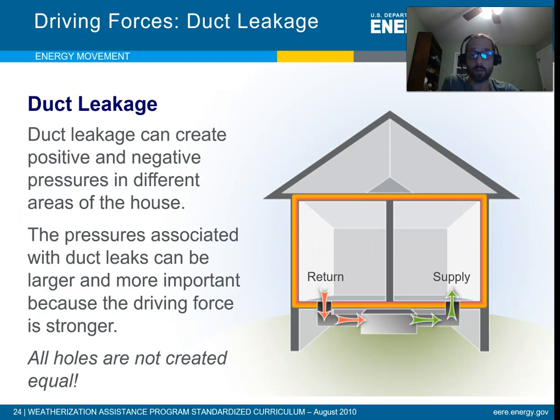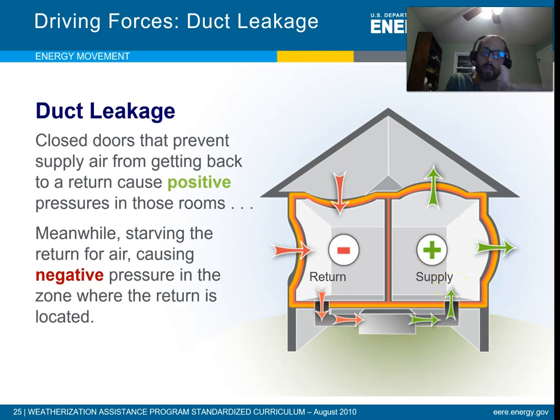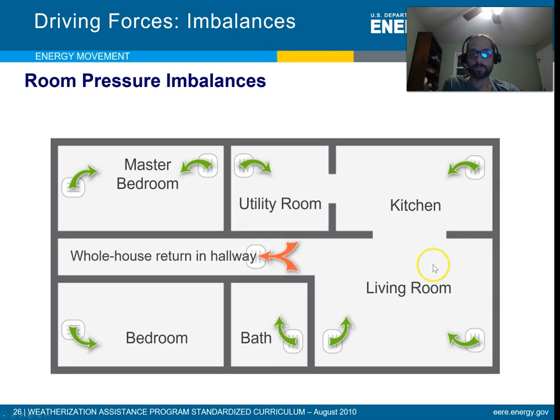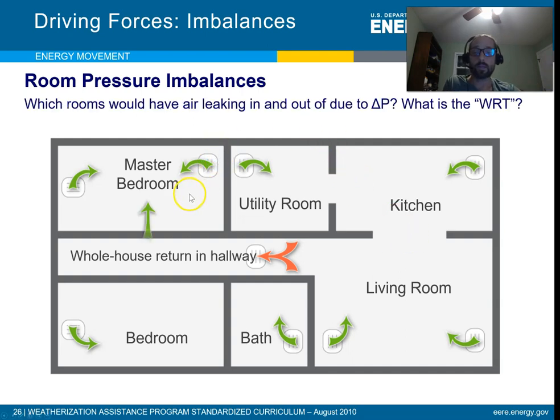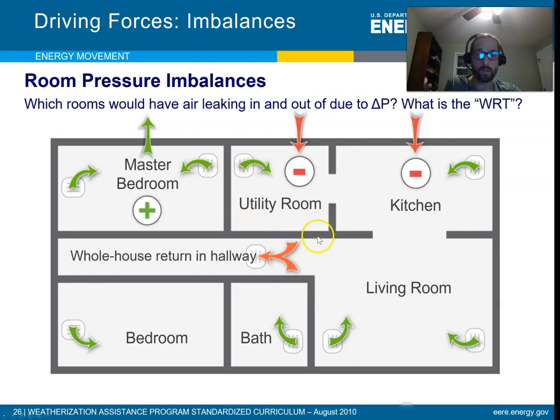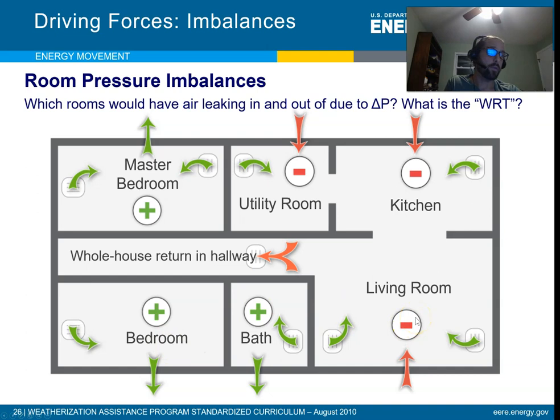Unbalanced ducts can also cause pressure differences. If you have two rooms — supply in one and return in the other — you'll have a positive pressure zone where the supply is and a negative zone where the return is. Ideally, every room should have both a supply and a return, which is something to look for in energy audits. Older buildings with one return vent for the whole floor create positive pressure zones in rooms with only supply and negative zones throughout the rest of the building, causing air to leak in and out.